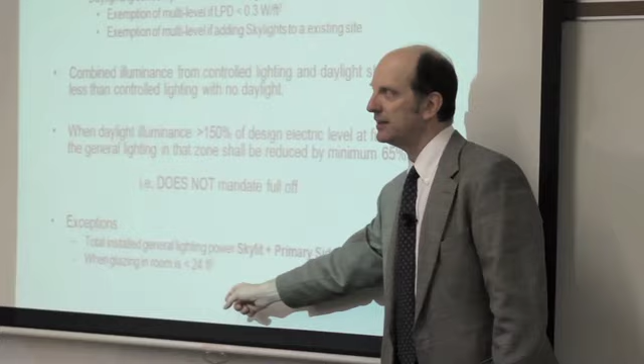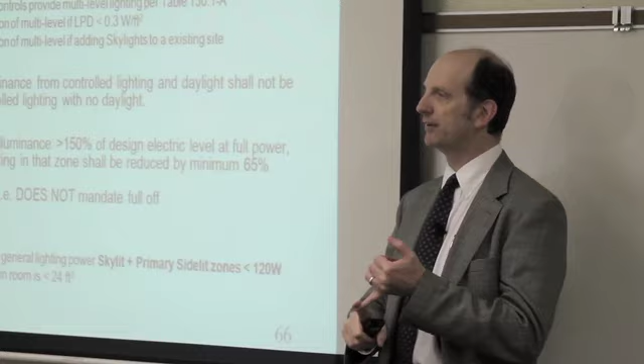Now, so here's the exemptions. Okay, so you've got to have automatic controls. The exemption before used to be you didn't have to do it if the side lit zone was 2,500 square feet. Okay, they changed that, and the new exemption now is if your skylit or primary side lit zones are less than 120 watts. So in this room, in addition to having the automatic off and the switch on the wall, and in this room, based on the lighting power density isn't low, you'd also have to have dimming control. You'd also need a photocell to control both of these fixture rows separately.